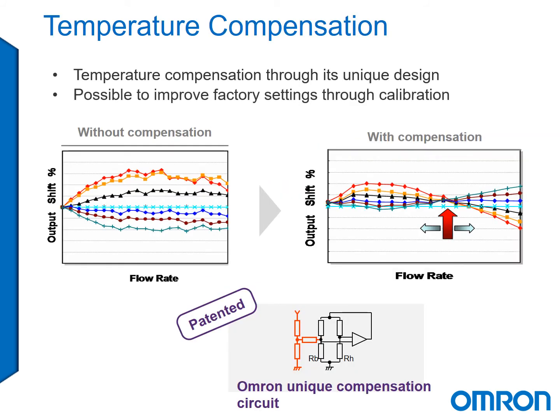Omron understands that in situations where temperature variance can occur, compensation is an important quality for a sensor to have. Through Omron's unique patented technology, we have ensured that compensation is possible. In fact, beyond the factory settings, it is possible for customers to improve the factory settings through calibration done in their own setup. As you can see in the charts below, without compensation, it is difficult to discern the flow rate of the application. However, with Omron's unique compensation circuit, we're able to get better readings and lower noise so that data can be easily discerned.